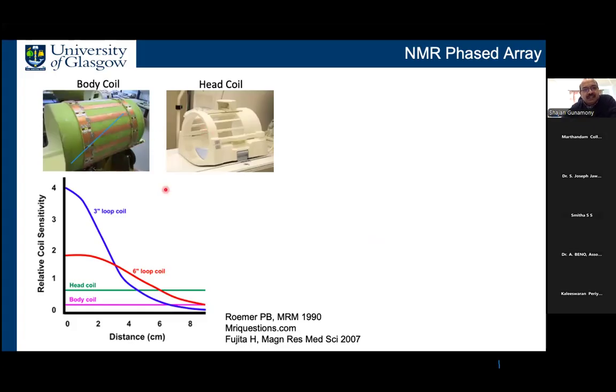So there's a large and small. Because the body coil is quite large, the sensitivity of this coil would be very weak because it's a large coil. But it is a flat response because it has a homogeneous field. Similarly, a head coil is smaller, so the sensitivity will be higher. Again, it will be a flat response because it has a homogeneous field.